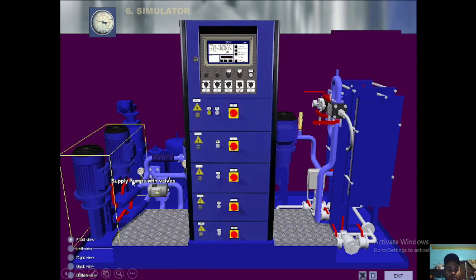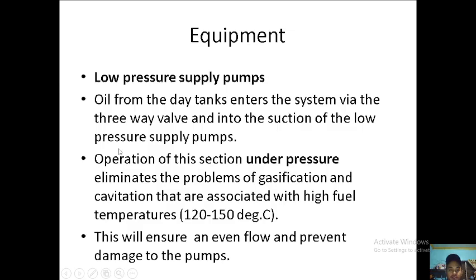Okay, next we have the supply pumps. We have two supply pumps, one on operation and one on standby. So the low pressure supply pumps: oil from the day tanks enters the system via the three-way valve and into the suction of the low pressure supply pumps. Operation of this section under pressure eliminates the problems of gasification and cavitation that are associated with high fuel temperatures, 120 to 150 degrees Celsius. This will ensure an even flow and prevent damage to the pumps. So we should always put the fuel under pressure by using our supply pumps, so that we can eliminate the problem of gasification and cavitation.